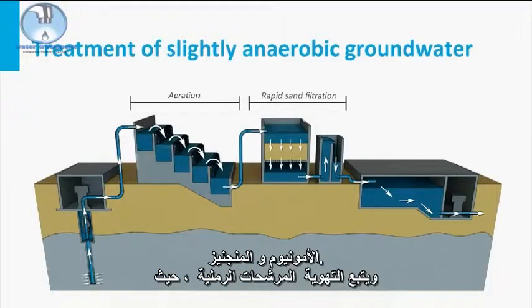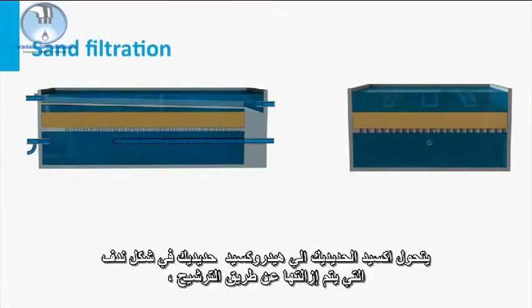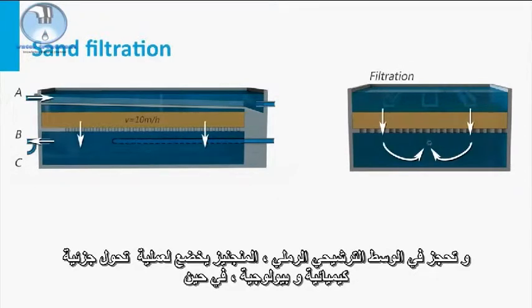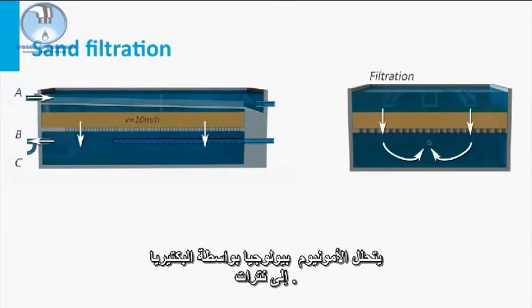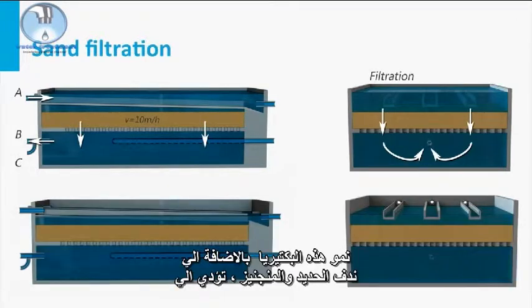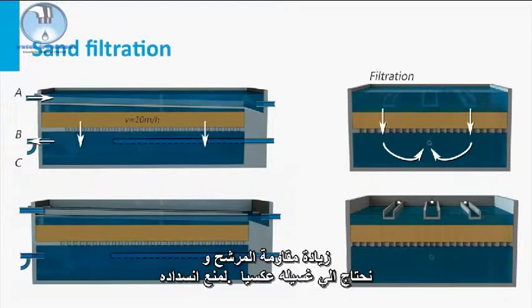Aeration is followed by sand filtration, where the oxidized ferric iron hydrolyzes to iron hydroxide flocs, which are removed by filtration in the sand bed. Manganese undergoes a partial chemical and biological transformation, while ammonium is biologically degraded by bacteria to nitrate. The growth of these bacteria in combination with the iron and manganese flocs results in an increase of filter resistance, and backwashing is needed to prevent clogging.